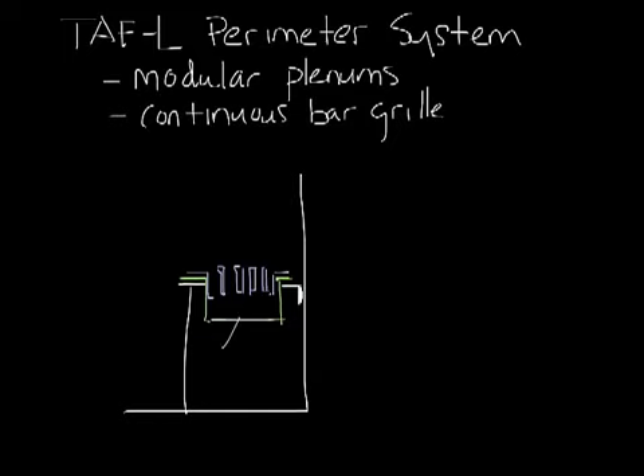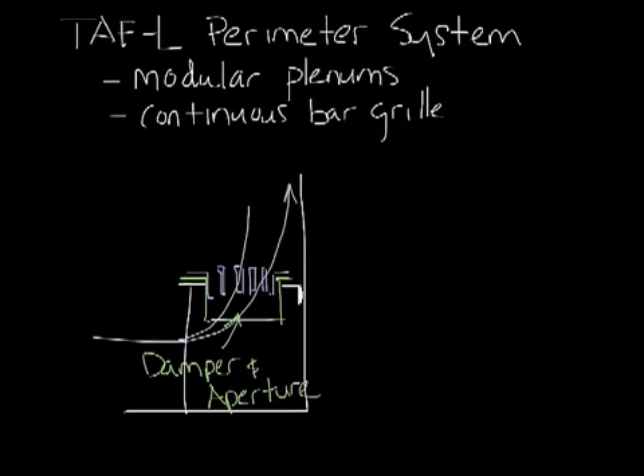So down here there is a damper. It's a sliding damper and an aperture plate. So as the damper slides across the aperture plate, it opens and closes the slots of the aperture plate, and it allows air to come through, and it varies the volume of it. As the air comes through the grill, the deflection actually changes as it moves away from the perimeter wall, and so you get a spread of the air pattern like this.